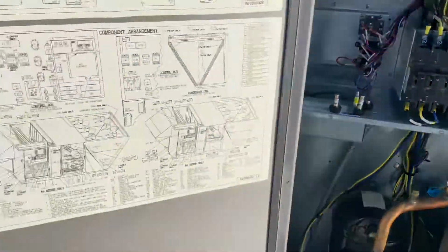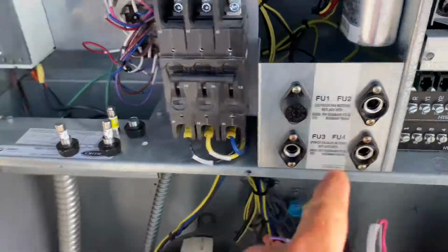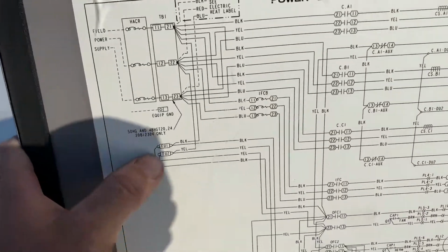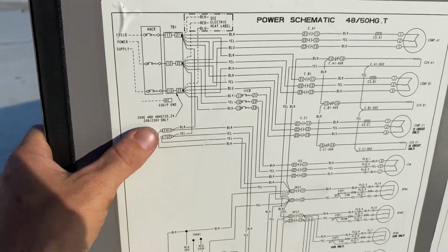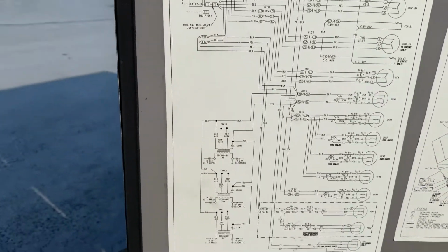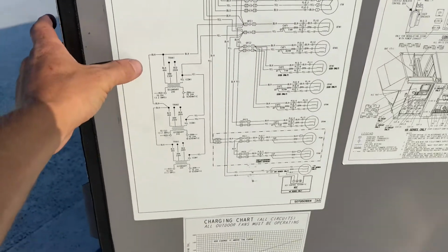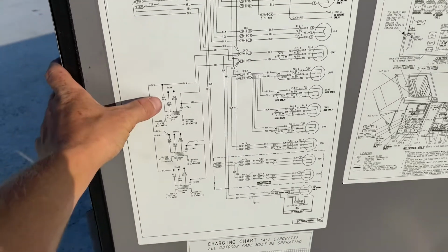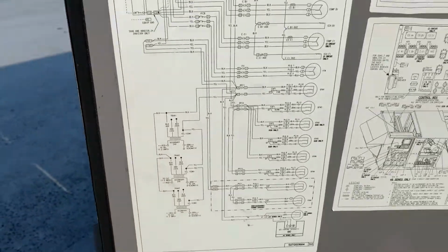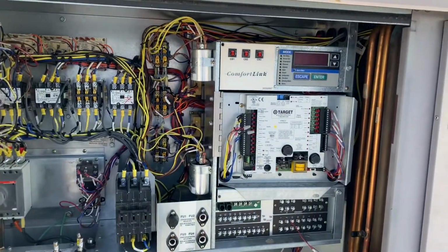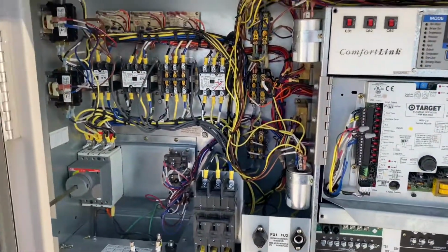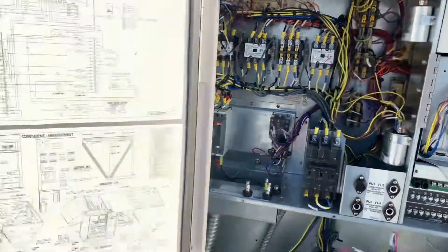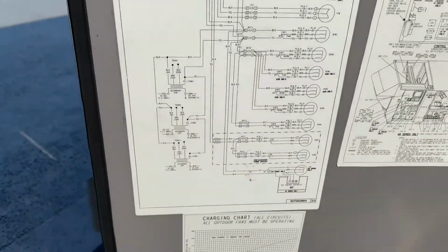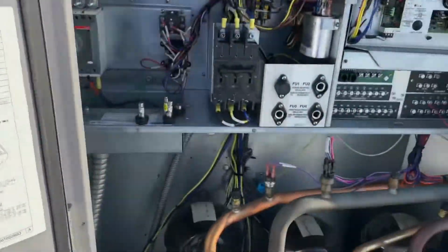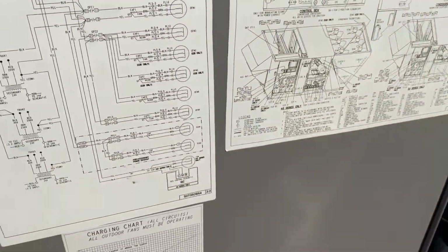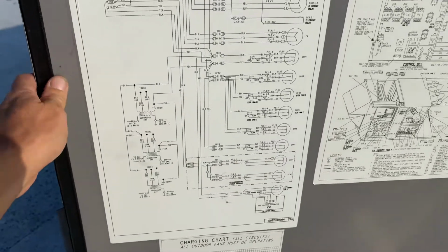So then went over to the wiring diagram, started with fuse 2. I found fuse 2 on the wiring diagram, and did some tracing, and see that fuse 2 is for the common side of all 3 transformers. So that's why I'm not getting any 24 volt control power to any of this as far as transformers, anything. So that's that issue. What caused it, we will find out. The other two fuses, fuse 3 and fuse 4, are both for the power exhaust.